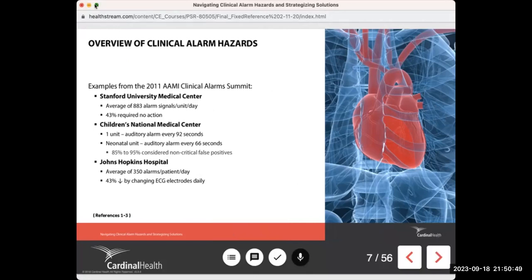Physiologic alarms are a common source of alarm hazards. In particular, physiologic alarms produce a high percentage of false or non-actionable alarms, resulting in little or no change in patient management. Consider a few examples from the 2011 AAMI Clinical Alarms Summit. Stanford University Medical Center reported an average number of 883 alarm signals per unit per day, and found that 43% of the alarms required no action.